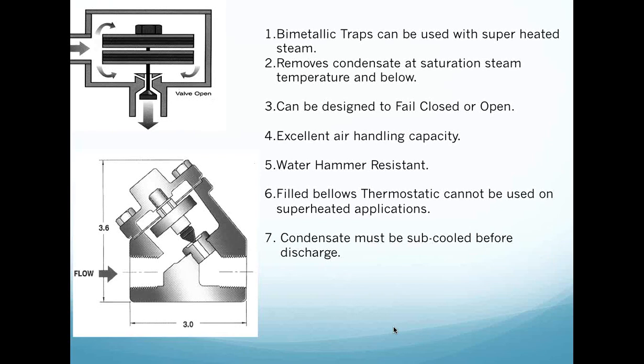So what would happen is that trap would cycle when it saw steam. It would close to trap that steam, hold it in the space, and it would cool, it would cool, it would cool. So it would bank that condensate up that would lay in that small zone, and that's where that degradation would be. These traps remove condensate at saturation temperatures and just below. They can be designed to fail closed or open. They're excellent at handling air.